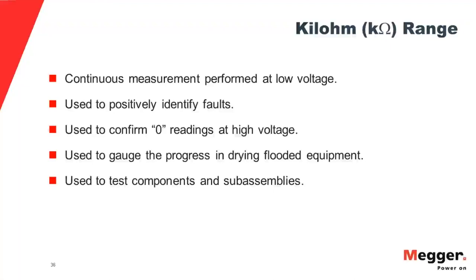And it's a very good feature in something like drying out flooded equipment, which in certain parts of the country, of course, and we've been hearing a lot of this in the news over the last few years, in certain parts of the country, this is huge. Equipment that has been underwater does not necessarily have to be replaced. It can be reconditioned. Drying it out is very important. And you can use your kiloohm range then to see what kind of resistance reading do you get when it's flooded, and then periodically check it as you're drying it out and see that it's becoming effective up until you get into the megohm range. And also, a lot of times components and subassemblies have lower insulation values because they're going to be buried inside a bigger piece of equipment where there is other insulation to protect the operator from ground. So the subassembly only needs to meet performance requirements, and they can be lower.